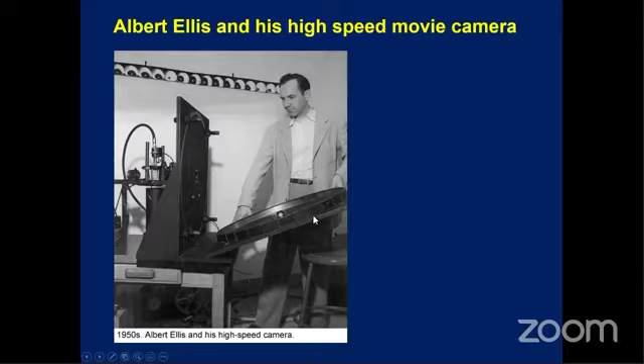And what happens when a bubble collapses next to a wall is that the side further away from the wall collapses in most rapidly, creating a re-entrant jet, which achieves very high speeds and impacts the other side of the bubble wall and the wall with a shock, a substantial shock. Now, in a region where cavitation is collapsing, it follows that the surface nearby is continually hammered by these collapsing re-entrant jets. Maybe that was an early explanation where people argued that this continuous hammering of the surface by these jets led to fatigue failure of the surface. The material flaked off, and these jets then started to work on the layer of material underneath that flake.